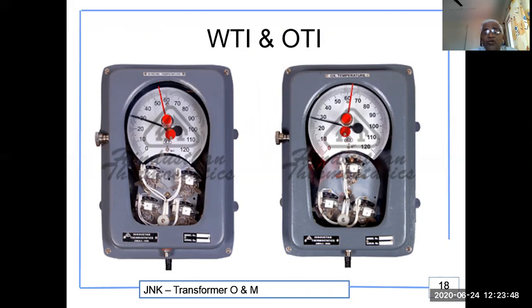The black needle shows the current temperature at the instant when you are seeing it. The red needle shows the maximum temperature it has touched after you have reset. So the reset you can do once every week, on Monday morning as you come for duty. So at the end of the week, you know how much is the maximum temperature it has recorded, both oil as well as the winding.